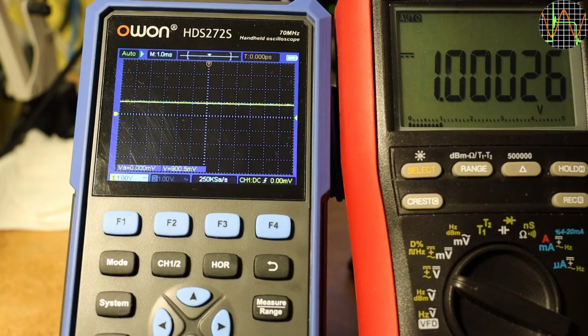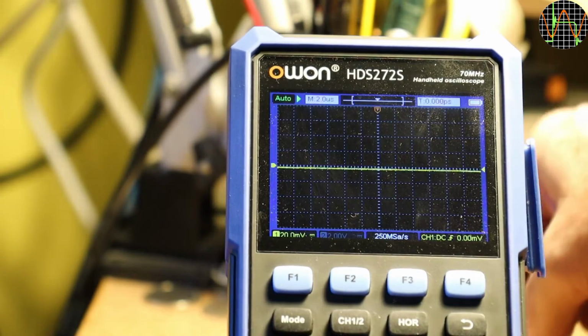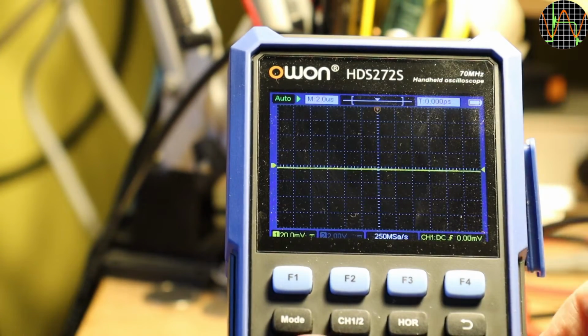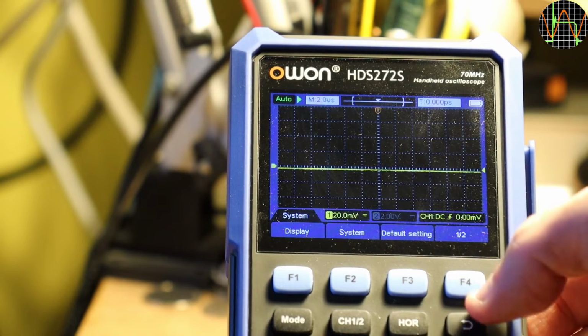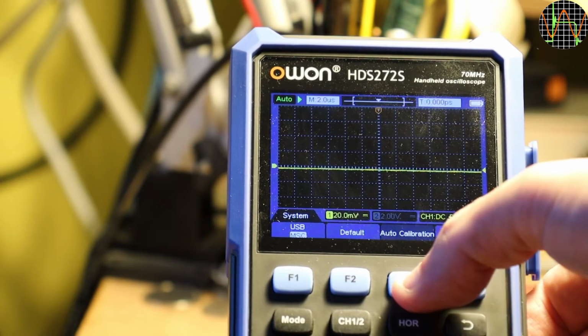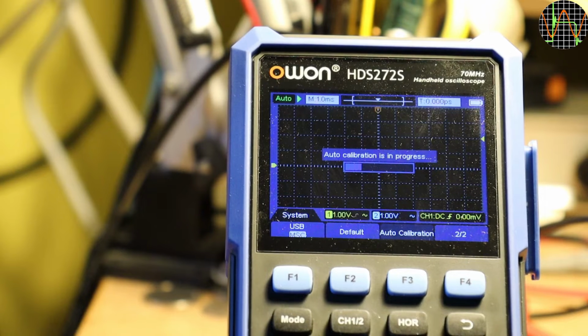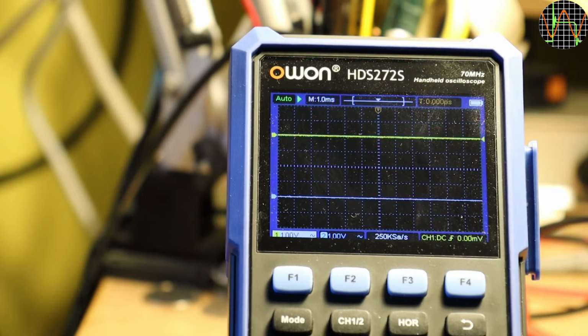The manual says if there is a temperature change of 5 degrees Celsius or more, you must run the auto calibration. That 5-degree change is practically guaranteed when you use the scope for more than a couple of minutes because it heats up internally. To do the auto calibration, you need to disconnect everything that is connected to the scope first. Auto calibration takes around 1 minute and I'm showing it accelerated. At the end it sets everything to defaults, so you may want to save your setup first before doing it.